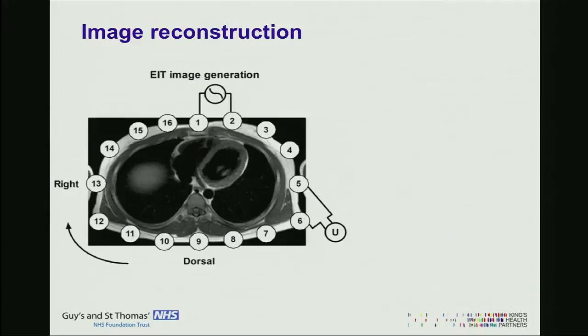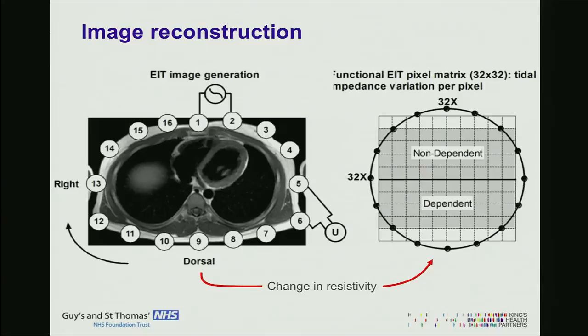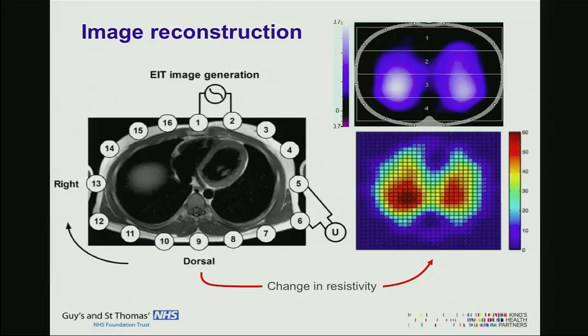Once all the resistivity measurements are performed, the EIT creates a 32 by 32 matrix. The whole lung field is divided into pixels, and each pixel has a value of resistivity which corresponds to a value of lung volume in that particular area of the lung. Through mathematical software, EIT generates an image scaled either as a color scale or a monochromatic scale, indicating change in resistivity from no change to maximal change. We can identify where this change in resistivity — and therefore volume — happens within the lung.